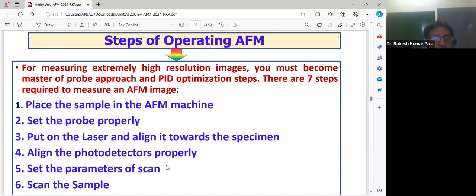And in the fourth step, align the photodetectors properly. Because in the earlier diagram we have seen, the laser beam falls over your cantilever, and after reflection this laser beam is detected by the array of detectors A, B, C, and D. So the alignment of the photodetectors must be proper. Basically this part is easier because the photodetectors are linked with your AFM, so we do not have the option to move them, but you have to take care.